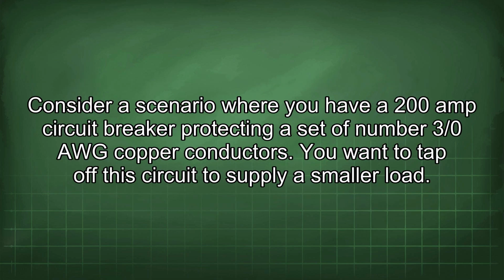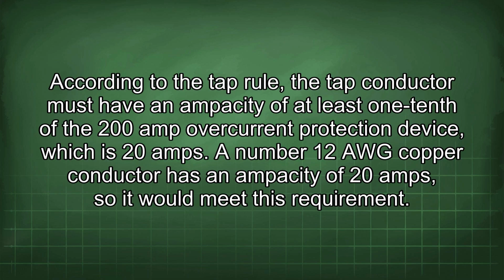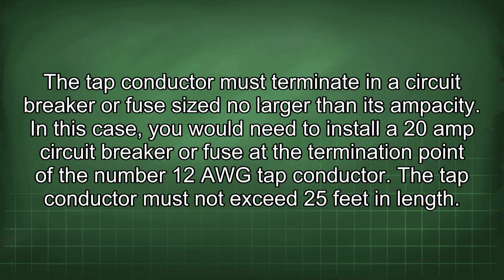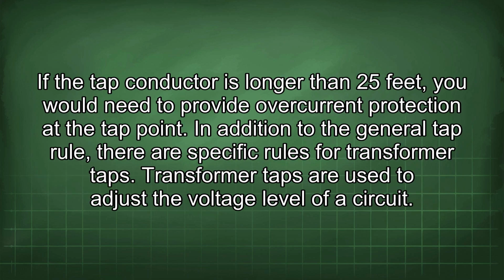Consider a scenario where you have a 200 amp circuit breaker protecting a set of number 3/0 AWG copper conductors. You want to tap off this circuit to supply a smaller load. According to the tap rule, the tap conductor must have an ampacity of at least 1/10 of the 200 amp overcurrent protection device, which is 20 amps. A number 12 AWG copper conductor has an ampacity of 20 amps, so it would meet this requirement. The tap conductor must terminate in a circuit breaker or fuse size no larger than its ampacity. In this case, you would need to install a 20 amp circuit breaker or fuse at the termination point of the number 12 AWG tap conductor. The tap conductor must not exceed 25 feet in length. If the tap conductor is longer than 25 feet, you would need to provide overcurrent protection at the tap point.